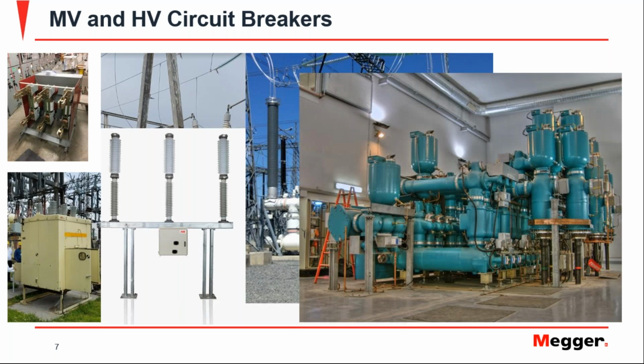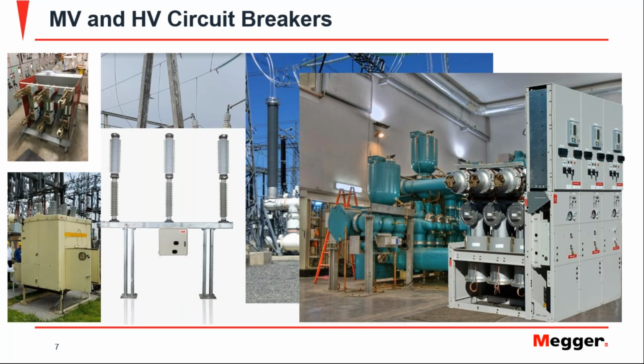And in the world of medium voltage and high voltage circuit breakers, we also have GIS substations, gas insulated. Of course, these have a circuit breaker as well, and it is subject to test as well. You can test these breakers, and as with any other electrical equipment, especially breakers, they may fail at certain points, so it's important to do maintenance testing. And in the GIS world, you also have medium voltage GIS substations, which are starting to be more and more common nowadays for distribution systems in small facilities, industrial and things like that.